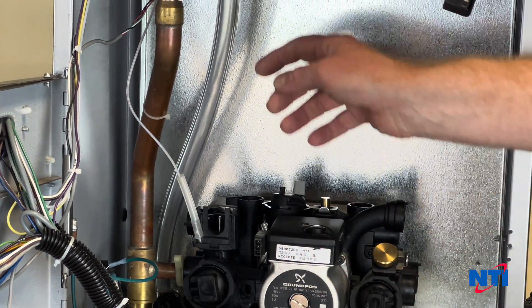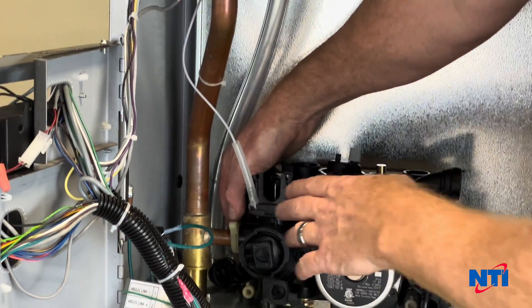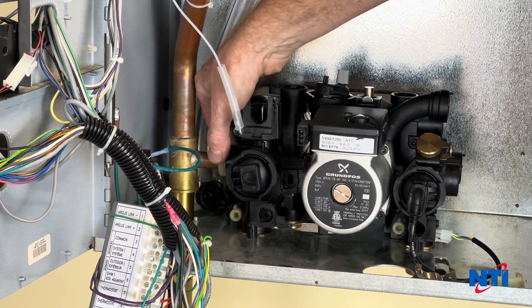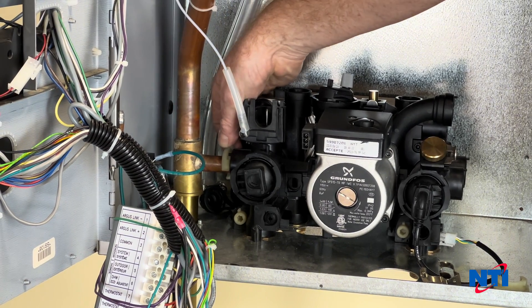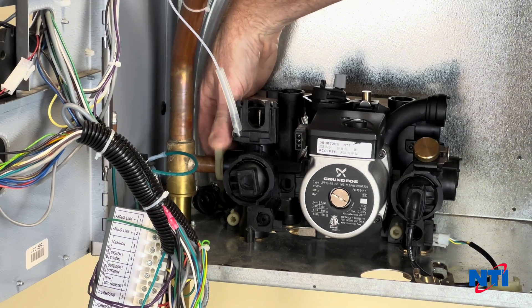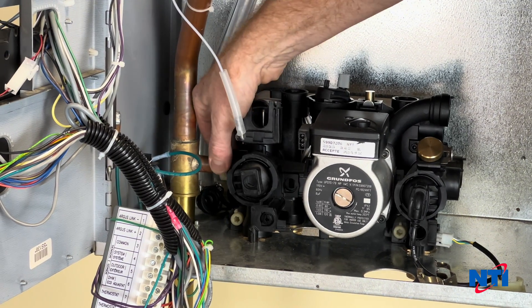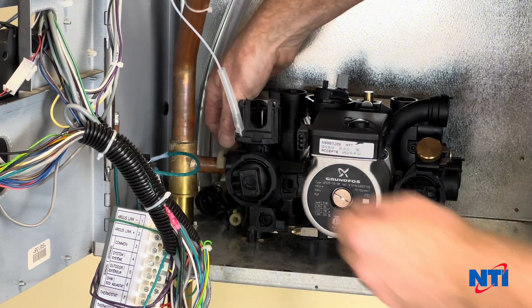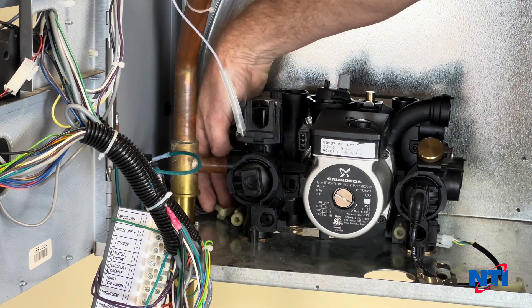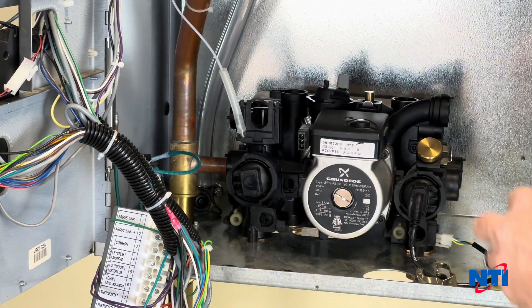Now that we have one pipe out, we're going to go to the left hand side. There's a second one of those teardrop style clips. If you push it back to the rear of the boiler that unlocks it, and pull it down to the front to lock it. So let's unlock it, slide it out of the way, and then lift it up and off the boiler.